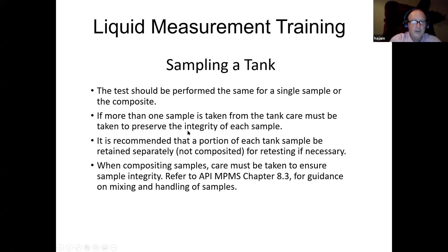One of the most important things you need to be aware of in taking samples is to preserve the integrity of that sample. Once a cap is put on the sample bottle, tag it with the pertinent information about time, date, maybe the batch number of the tank, or the liquid in the tank, if it's done by batch or by monthly ticket. You want to put all the information you can on that sample tag so that the sample can be identified. And also you need to keep a spare or reserve sample just in case questions arise.